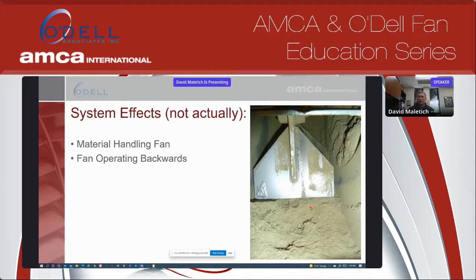This is not actually a system effect, but this is kind of a reminder that three-phase motors can be wired. You have a 50-50 shot that you're going to wire a motor either clockwise or counterclockwise in its rotation. In this case, this is a dust handling system. Customer felt at the end outlet of the fan, air was being moved, so they assumed that it was rotating the wheel in the correct rotation. However, the rotation was backwards. And it was still fast enough in order to capture the dust. However, it wasn't fast enough to convey the dust in the system. So the dust dropped out in the ductwork, dropped out in the fan. Unless their load calcs are way overdone for supporting their ductwork, it's a pretty unsafe situation in which you have overloaded duct with a lot of dust inside of it that could collapse and cause some injuries on the shop floor.